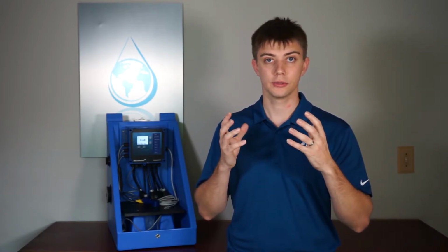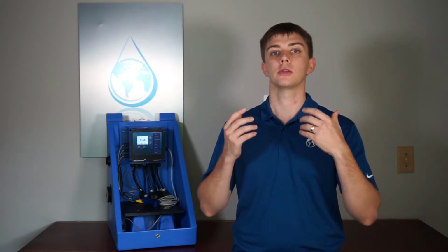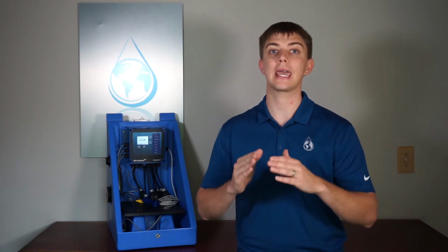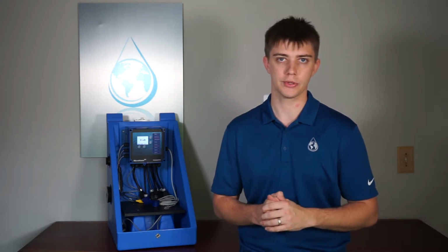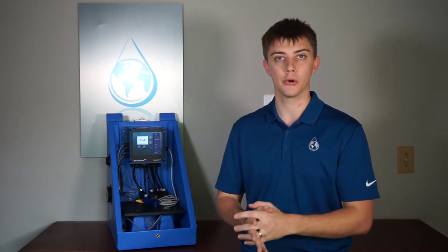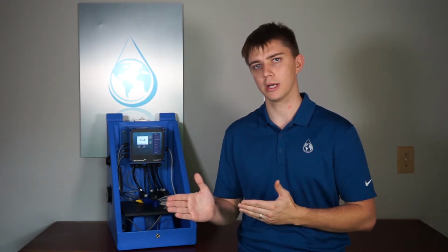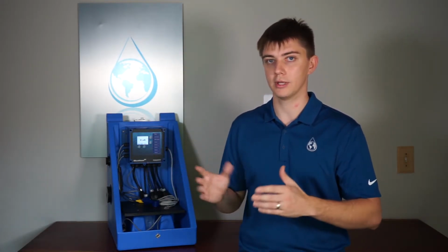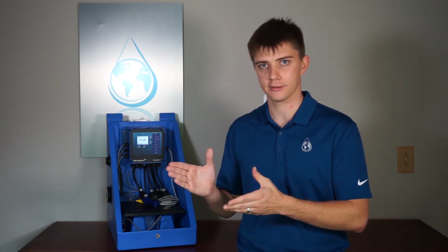With a set point control mode timer, where you define rising or falling, you also have to define the set point that I mentioned, and a differential. You can define a limit alarm. I recommend this on any relay that's feeding product. If you've got set point control mode set up with a PTSA probe and you're feeding inhibitor, you would not want something to happen to your probe reading, or somehow you have no flow maybe and the probe might be drifting. It could cause you to overfeed and potentially dump a whole chemical drum into your process.